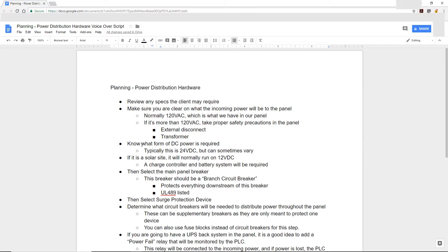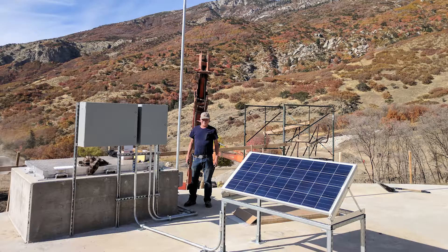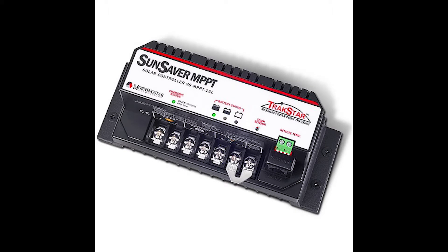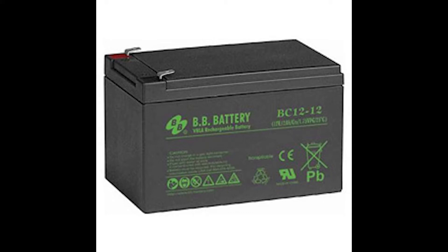The next thing we want to look at is what type of DC power is going to be required in our specific control panel. Typically in the panels we build, we're going to use 24 volts DC, but that's not always the case — this can vary up or down depending on your specific application. For example, if we're going to be at a solar site, solar panels generate 12 volts DC, so those panels often operate on a 12 volt DC system with no AC voltage at all. If you are going to be on a solar site, you also need a charge controller and some sort of battery system to make sure the control panel can continue to operate even when the sun is down.